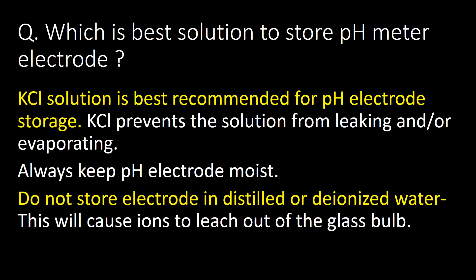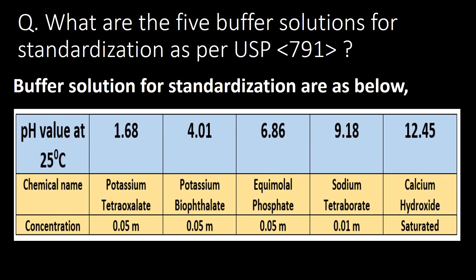Which is the best solution to store pH meter electrodes? KCl, that is potassium chloride solution, is best recommended for pH electrode storage. KCl prevents the solution from leaking or evaporating. Always keep the pH electrode moist and do not store the electrode in distilled or deionized water, as this will cause ions to leach out from the glass bulb.